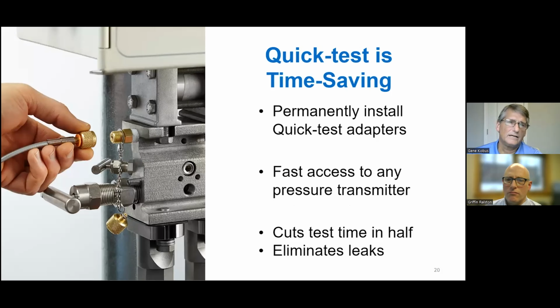Time savings. Customers who permanently install quick test adapter with a cap and chain on each of their pressure instruments in their facility will have fast access whenever they need to calibrate their device. This cuts test and calibration time in half because it eliminates all setup time. This also eliminates leaks due to repeated use of thread tape and wrench tightening of adapters.